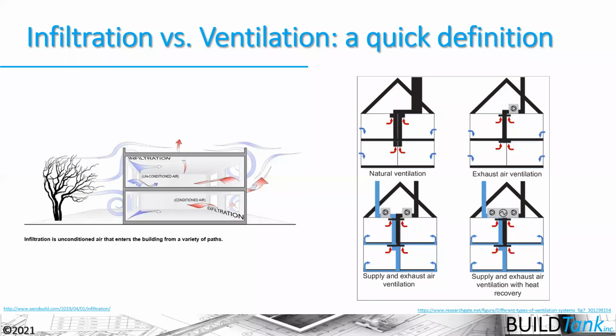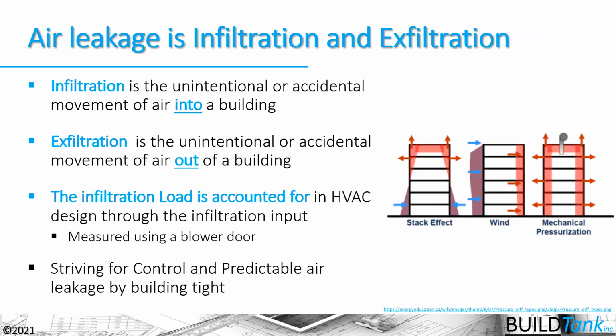So we want to make sure we understand infiltration and ventilation and how they're different from each other. Infiltration and exfiltration are that part of air leakage that is unintended and accidental. This unintended and accidental movement of air across our building thermal envelope. Air in is infiltration, air out is exfiltration. These also create loads, because again, we have to heat and cool that air that's coming in and out of our house. So there's an HVAC load that's calculated through this.